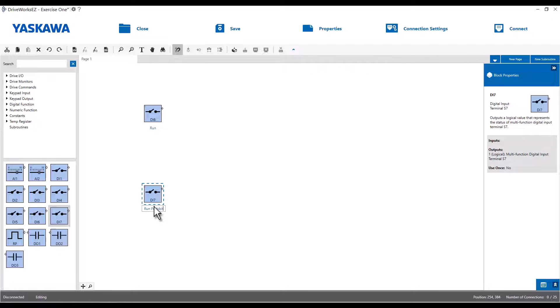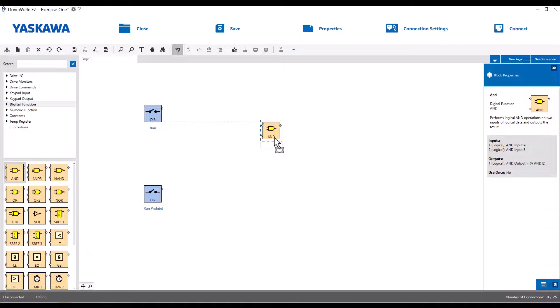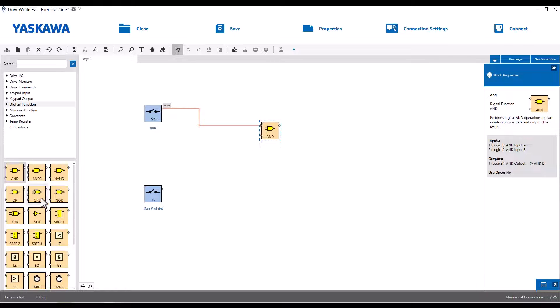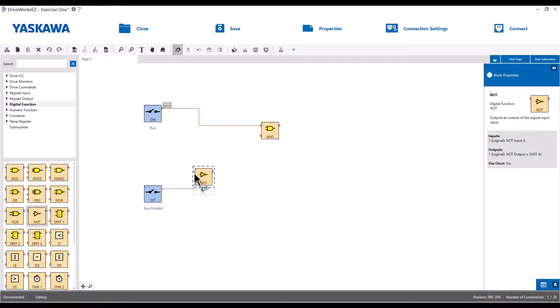Now for this program, we're going to use an AND block, so that's going to be under the digital functions. Just drag the AND block onto your screen. So the customer wanted the drive to only run if terminal S6 is closed and S7 is open. So that means we'll just run digital input 6 straight into the top input of the AND block, but we want this run prohibit to be the opposite. So we're actually going to put a NOT gate between the DI7 block and the lower AND block input. So if that one is not closed and digital input is closed, it'll run the drive.